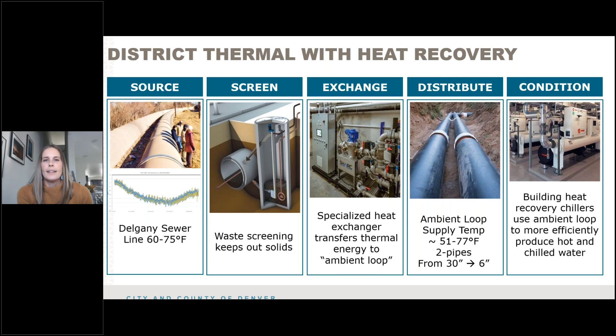At each building, the ambient loop is sent to the heat pump chillers, and then we route it to the chiller's condenser side first to produce cooling from the evaporator for the chilled water loops, or to the evaporator side first and then reject heat from the condenser to the building's hot water loop. And then each chiller can be in either heating or cooling mode, so we can do both at the building. And those systems can leverage each other, which is pretty neat. Next slide. Then we have just an overview of what the central plant will be doing.